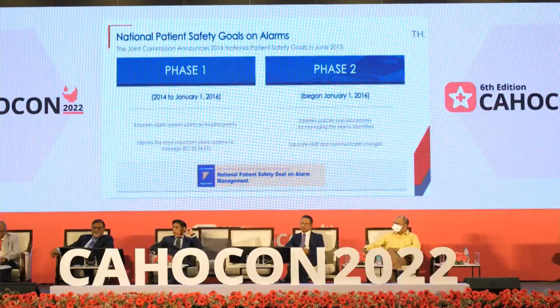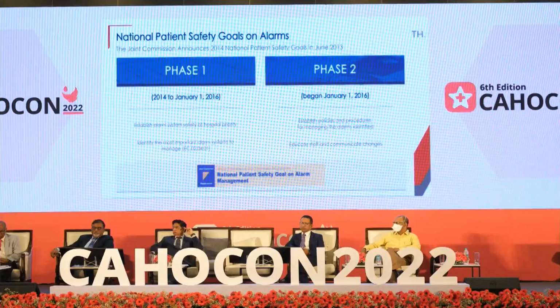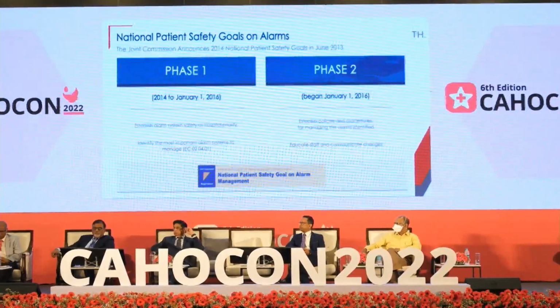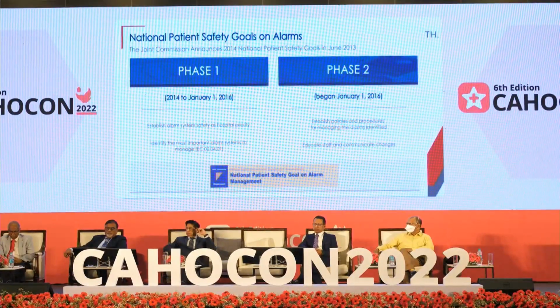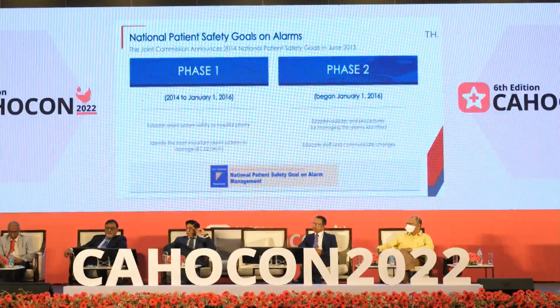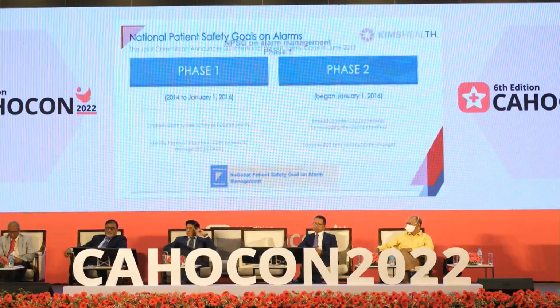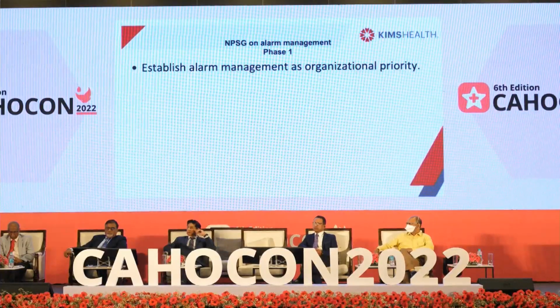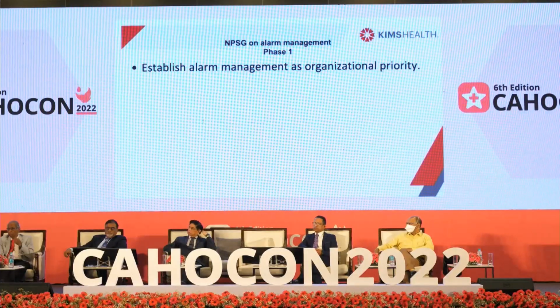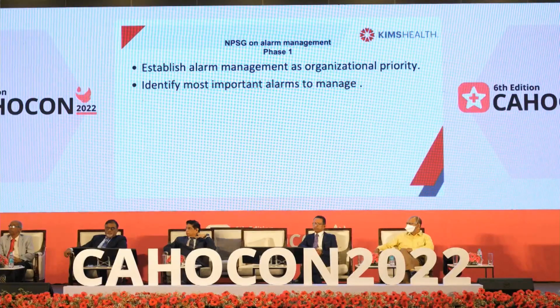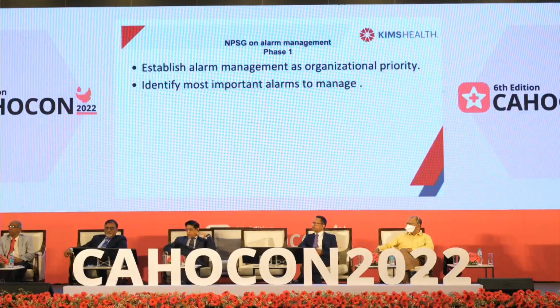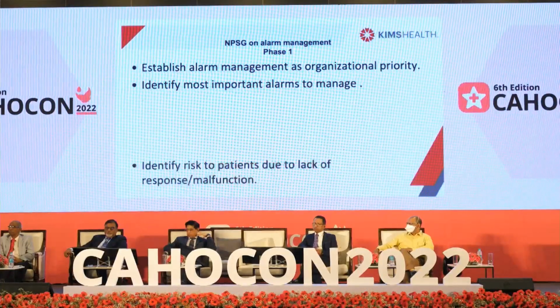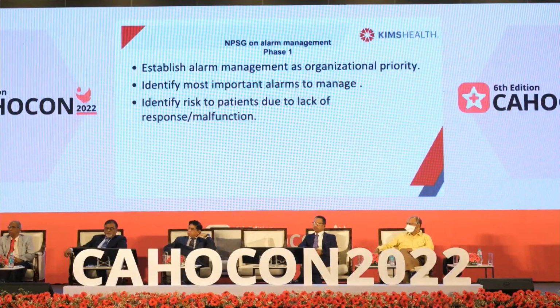The National Patient Safety Goals proposed by JCI aim to decrease alarm fatigue, and they plan to implement it in 2 phases: phase 1 from January 2014 to 2016, and phase 2 from January 2016. The elements are: leadership should establish alarm management as an organizational priority, and identify the most important alarms to manage, because some patients will have many alarms which are not indicated for them, or may have monitors which are not required for them. Identify risk to patients due to lack of response or malfunction. Identify actionable versus nuisance alarms, and publish best practices and guidelines.